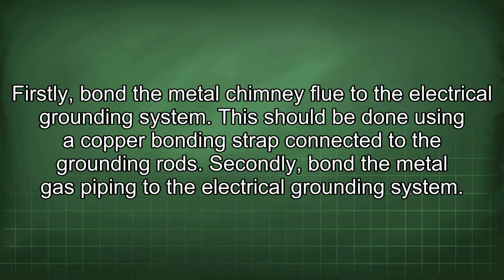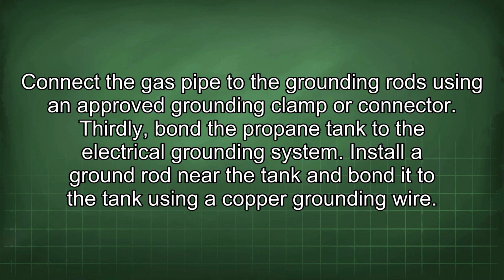This should be done using a copper bonding strap connected to the grounding rods. Secondly, bond the metal gas piping to the electrical grounding system. Connect the gas pipe to the grounding rods using an approved grounding clamp or connector. Thirdly, bond the propane tank to the electrical grounding system. Install a ground rod near the tank and bond it to the tank using a copper grounding wire.